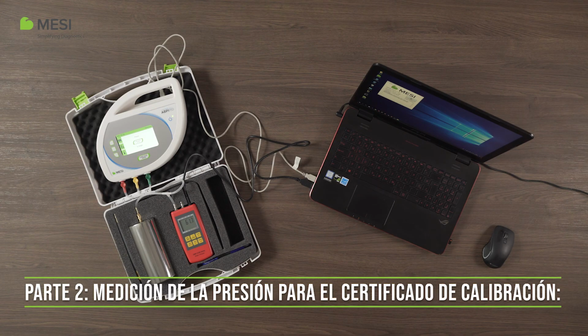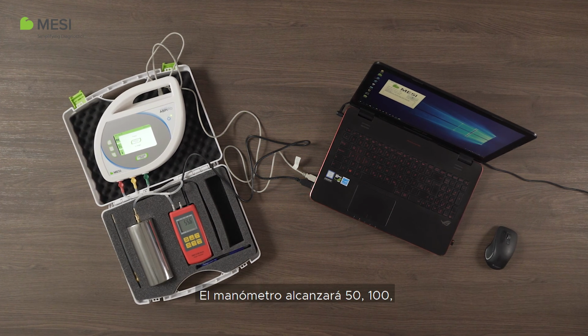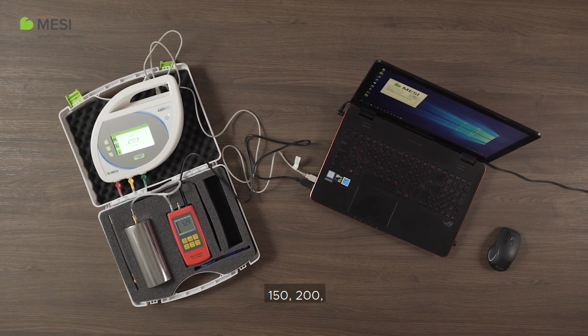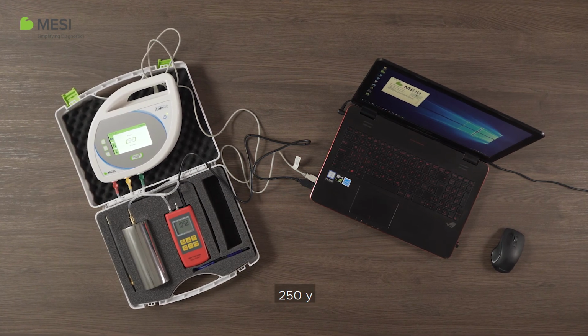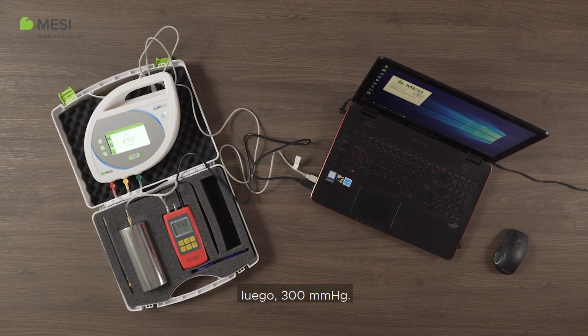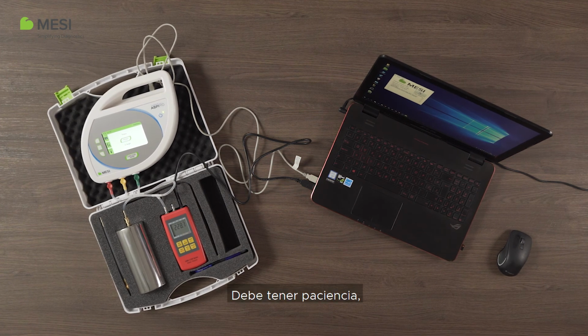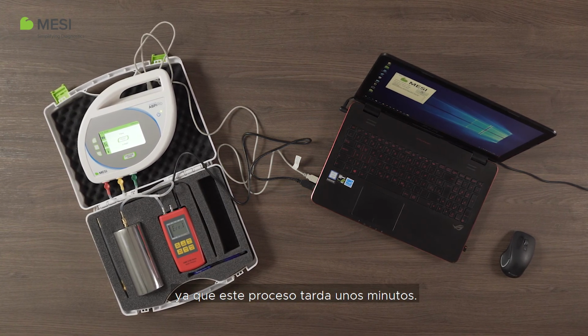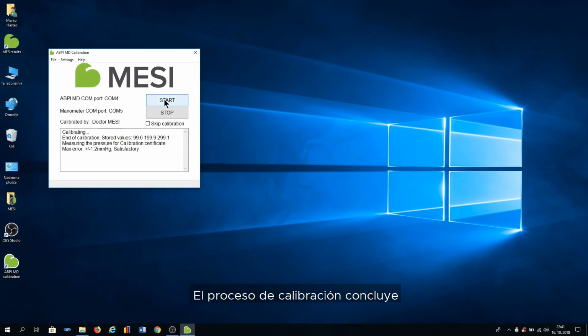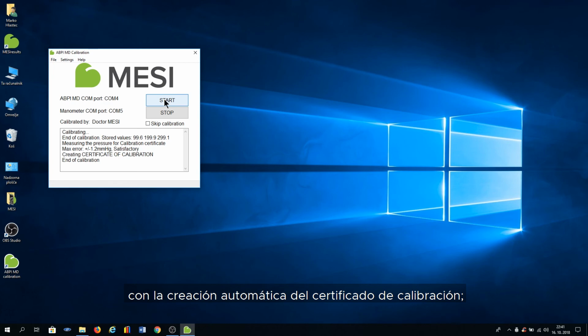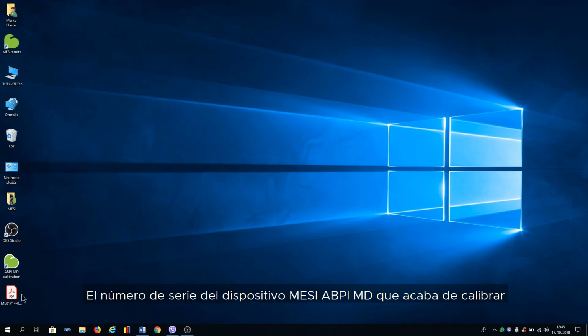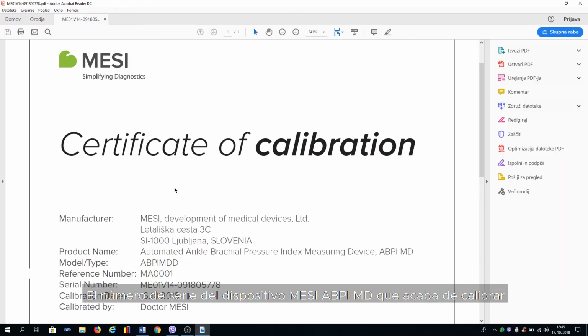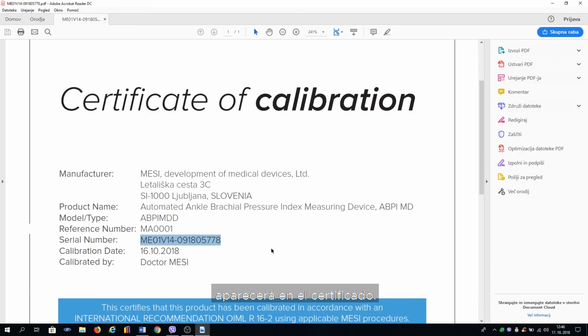Part 2. Measuring the pressure for the calibration certificate. The manometer will reach 50, 100, 150, 200, 250, and then 300 millimeters of mercury. Be patient, this process takes a few minutes. The calibration process is concluded with the automatic creation of a calibration certificate. An icon will pop up on your desktop. The serial number of the MESI ABPI MD device you just calibrated will appear on the certificate.